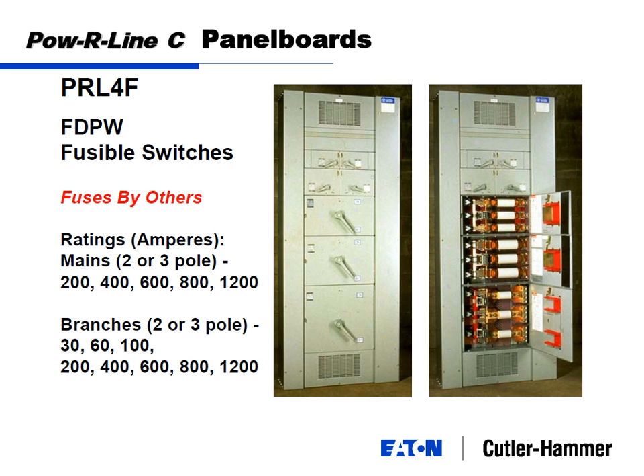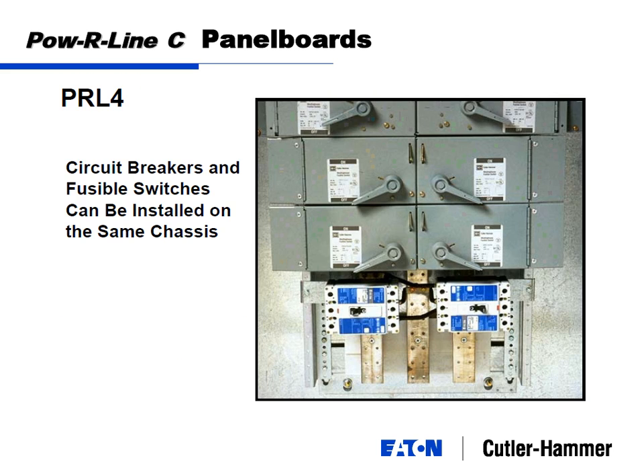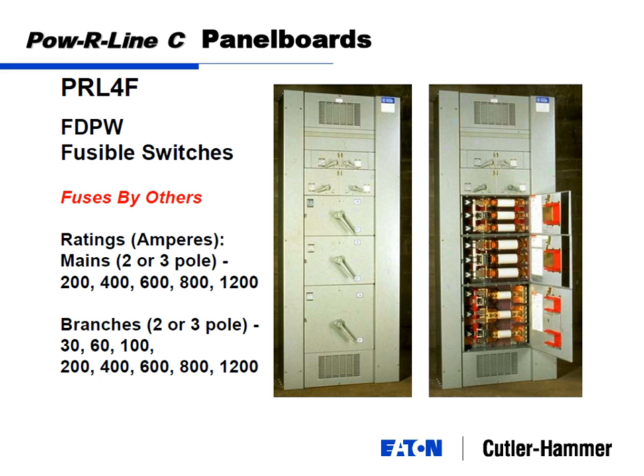And that's just, again, it gives you a view of what it looks like on the inside of that. You'll notice one of the other things I want to point out: on these Powerline 4s, there's no door because they're power distribution panels. You don't have a door that locks this dead front from all the circuit breaker panels. You are pretty much looking at just a dead front trim where your handles or your operating mechanisms are all facing. Now it is a distinction.